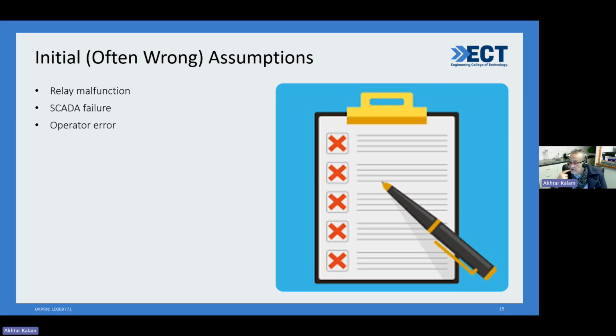My second assumption is that the SCADA failure was there, and therefore incorrect information was given to the CTs and VTs, and therefore the relay sent a signal for the circuit breaker to operate. That did not happen either. And the third, which is a great possibility, is that there was an error on the part of the operator. Human errors are the worst thing that can happen. If you look at CIGRE, they say 60% of faults are due to human errors. All these three assumptions that I have made, whether it's of the relay, the SCADA, or the operator, all of them are incorrect.